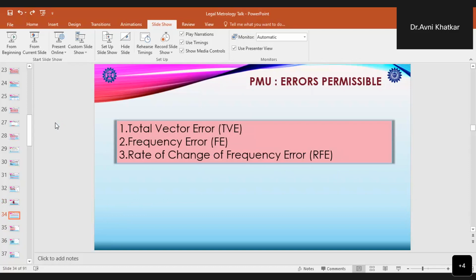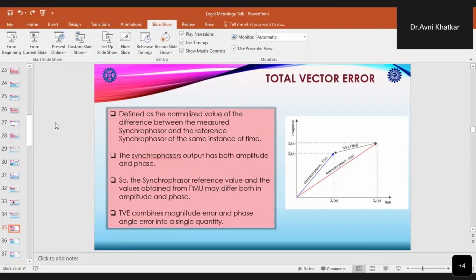Now, when we talk about PMUs, we talk of the errors in three quantities: total vector error, that is TVE, frequency error, that is FE, and rate of change of frequency error, that is RFE. So we will see all these here. First one is total vector error. Total vector error is defined as the normalized value of the difference between the measured synchrophasor and the reference synchrophasor at the same instant of time. These synchrophasor outputs have both amplitude and phase, so the reference value and the values obtained by the PMU may differ in both amplitude and phase. And total vector error combines both the magnitude error and phase angle error into a single quantity.